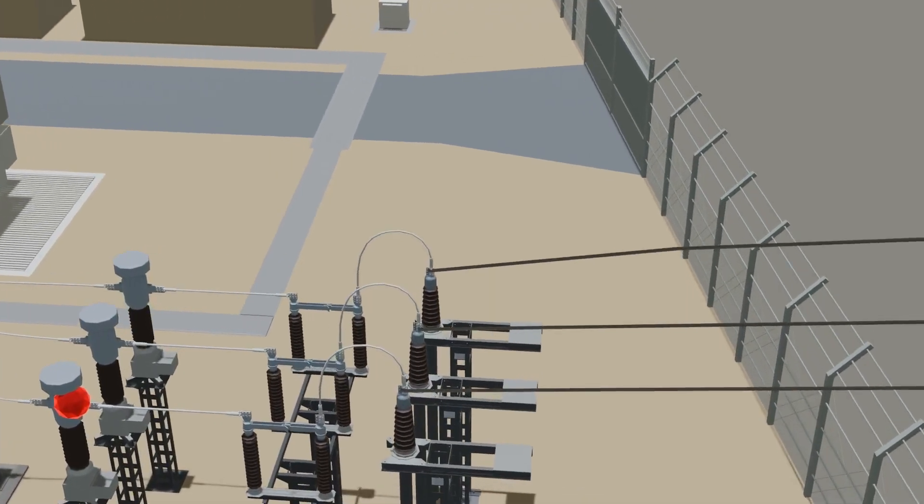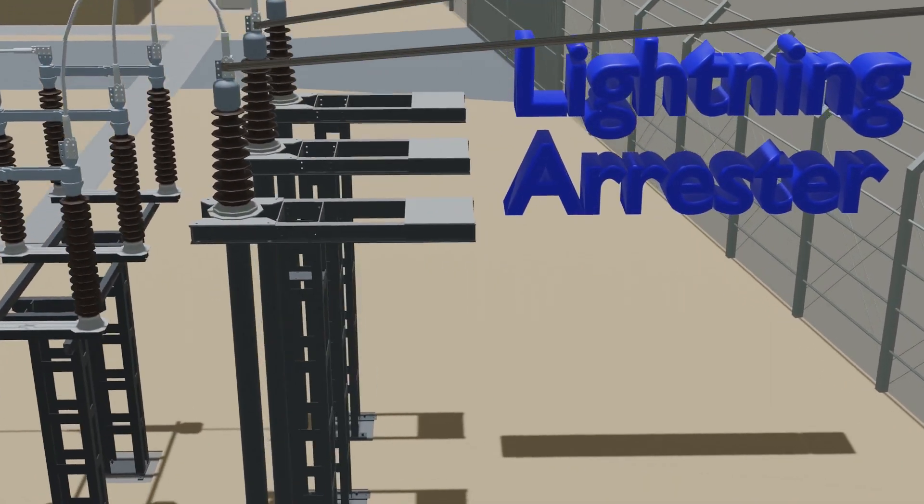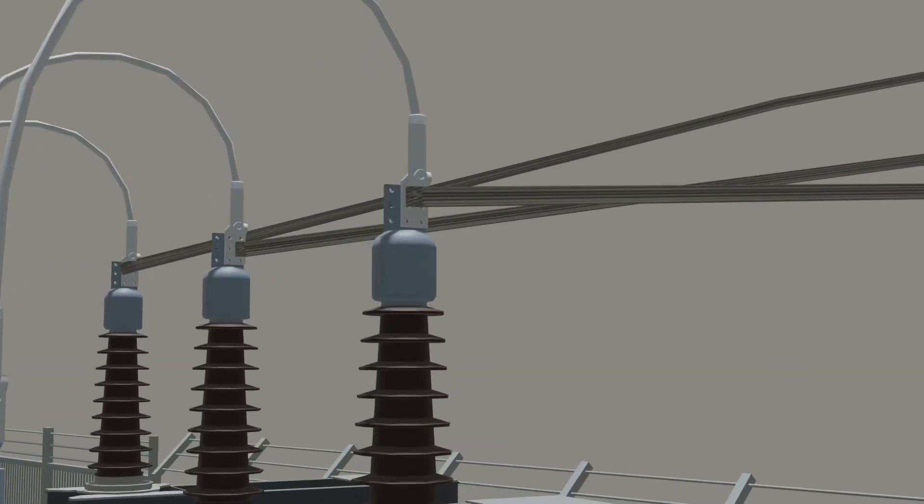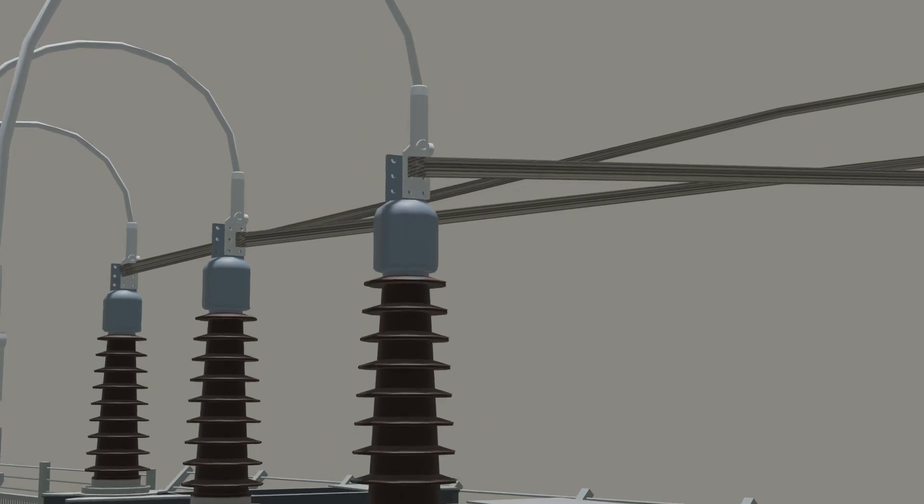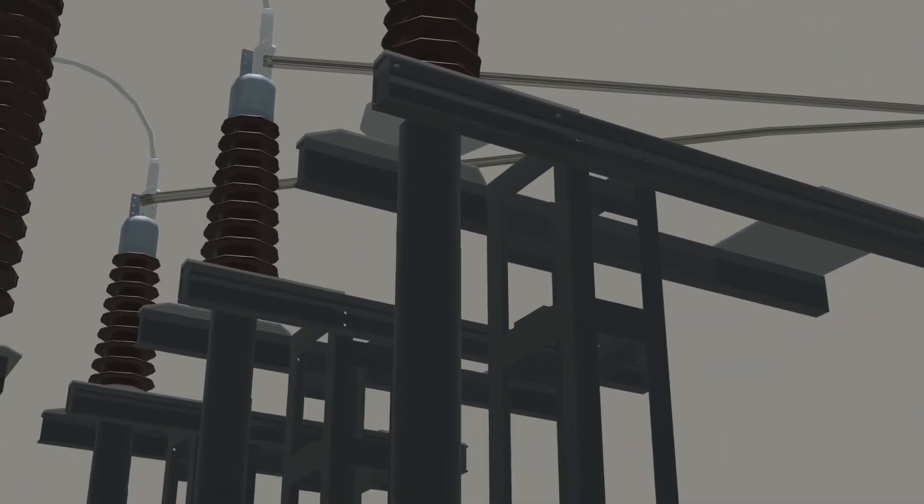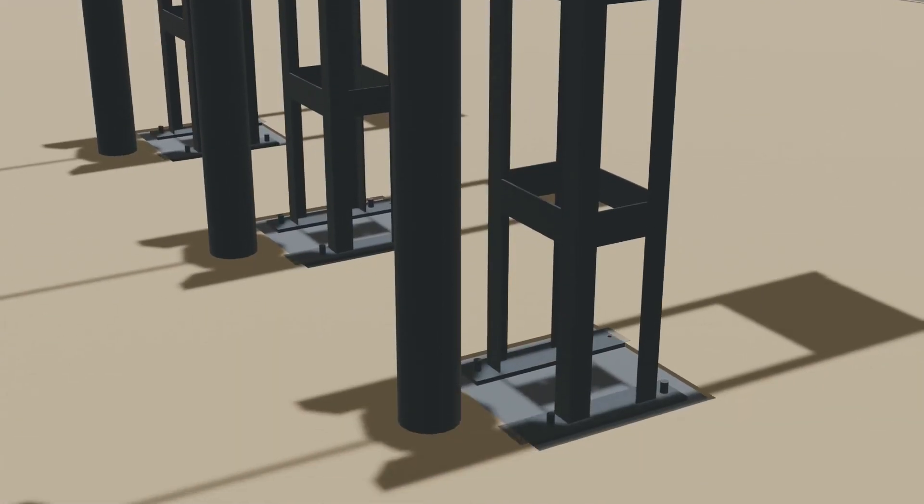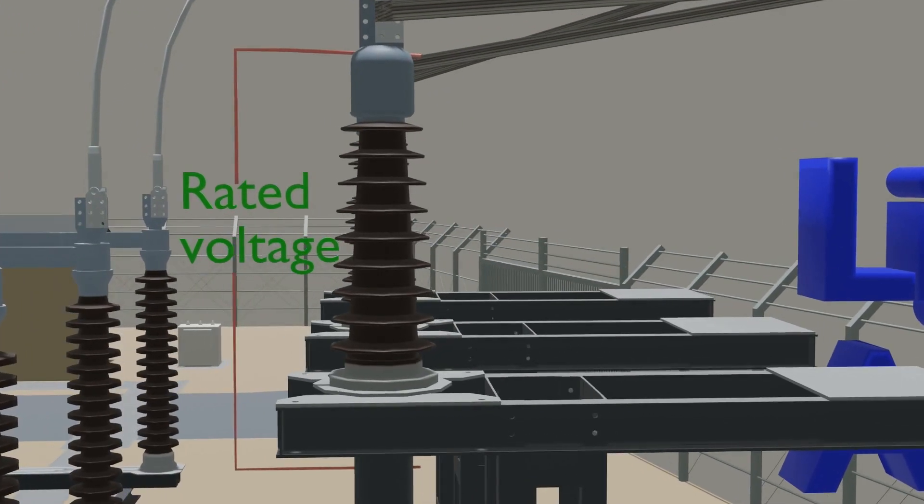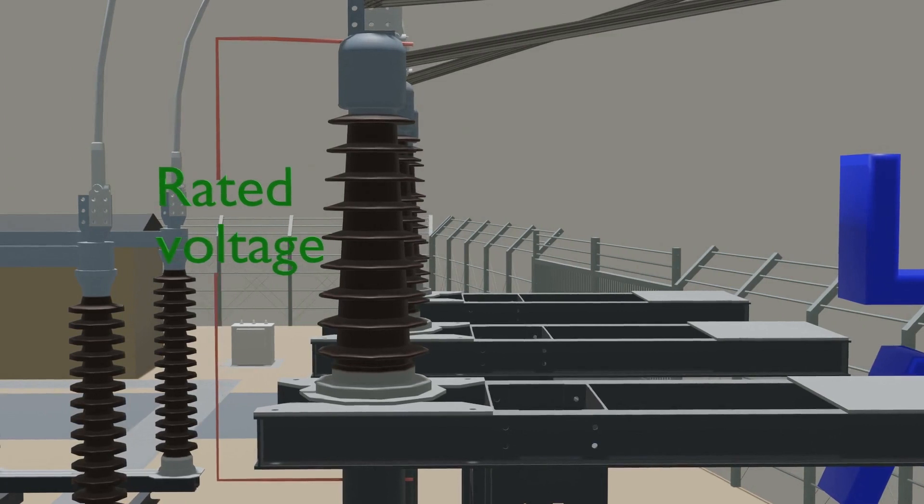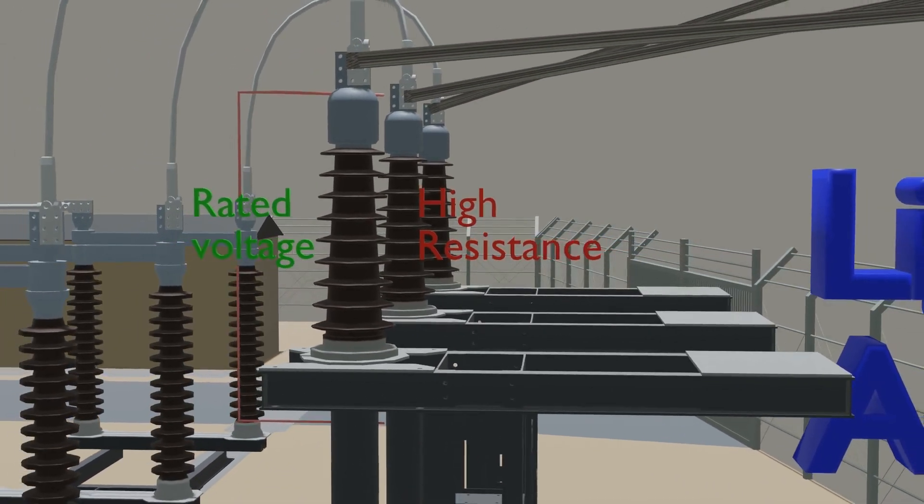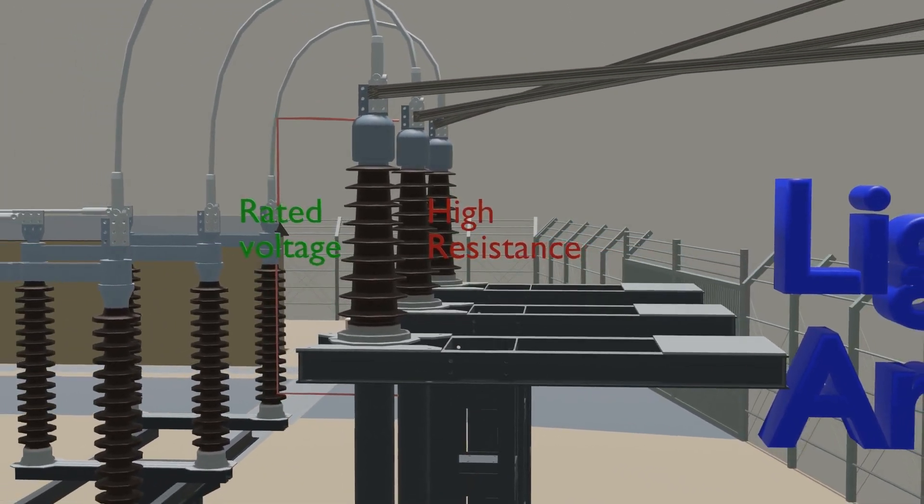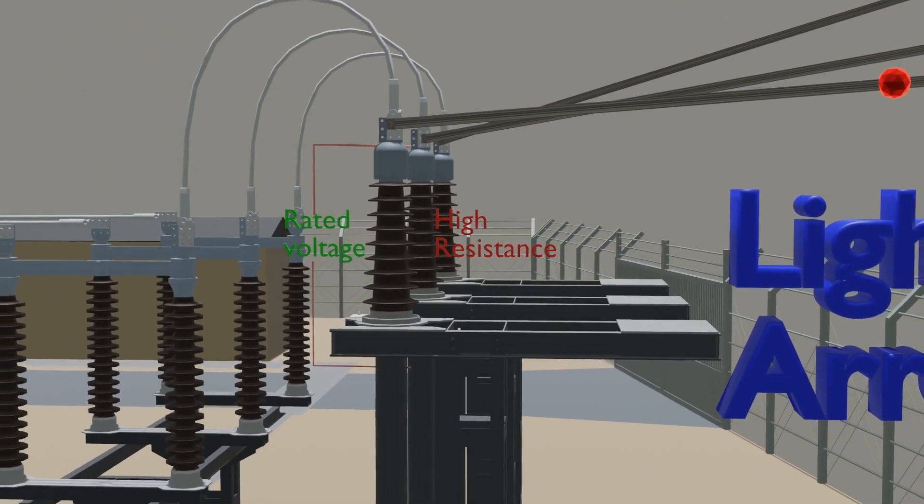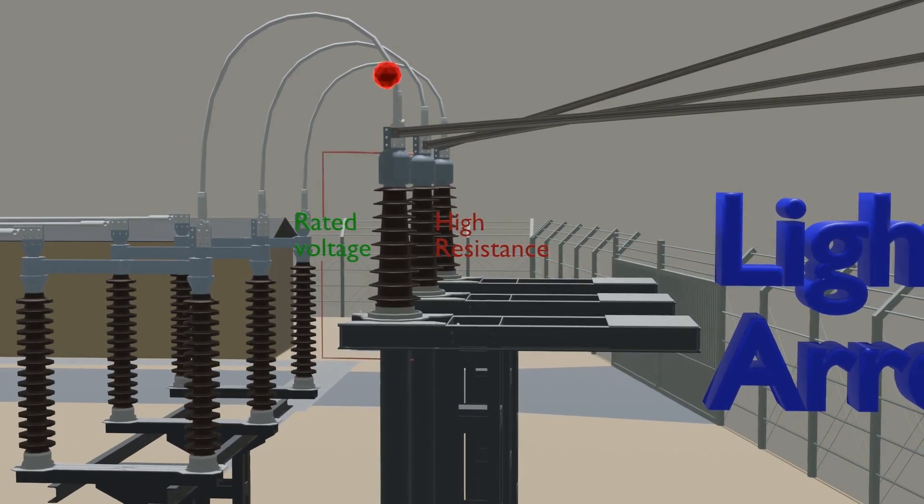The first equipment in substation is Lightning Arrester. One terminal of Lightning Arrester is connected with the phase and another terminal is connected directly to the ground. In normal condition, voltage across the Lightning Arrester is rated voltage, so it provides high resistance. And due to that, current does not flow inside the Lightning Arrester but directly goes inside the substation.